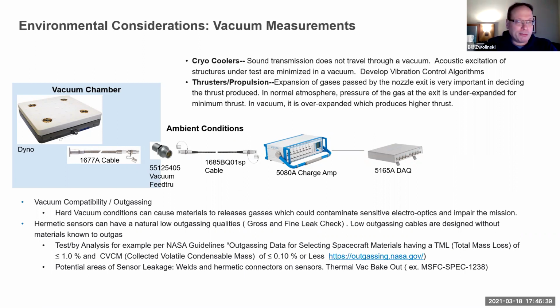In terms of doing vacuum testing, it's always important to have what's called low outgassing components. And outgassing is actually what it appears to be. Some materials disperse material that can be deposited on very sensitive optical systems, for example. So pre-baking or doing a thermal vacuum bake-out is often one of the first rules before you put any sensitive hardware and any instrumentation into a vacuum chamber. So low outgassing is very critical to vacuum measurement.